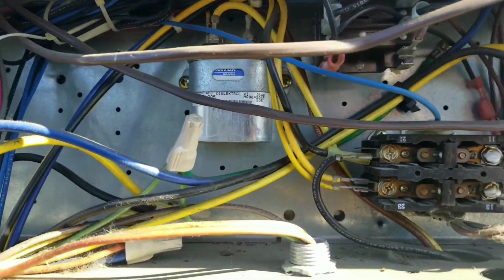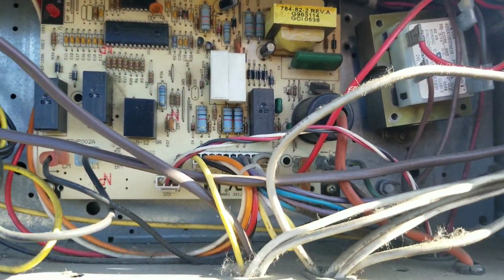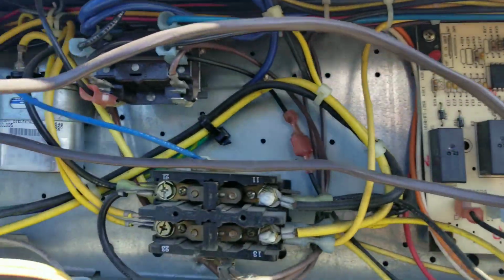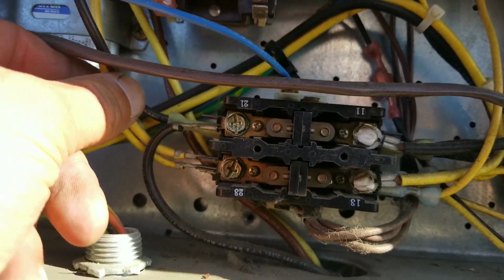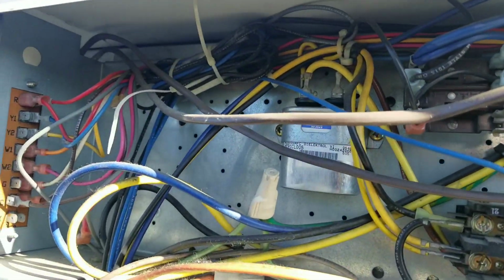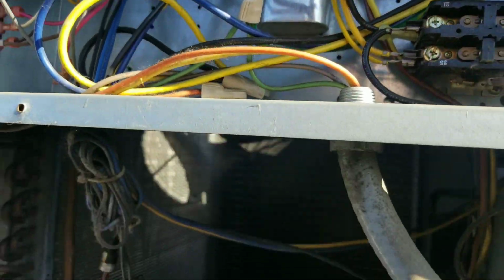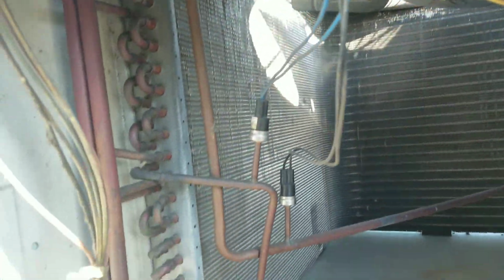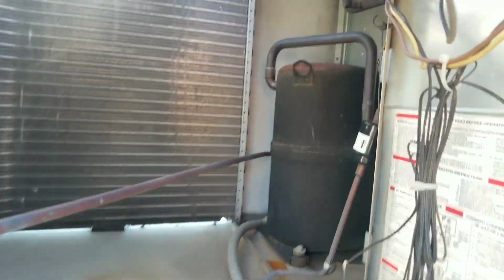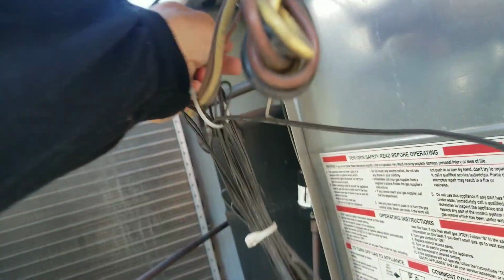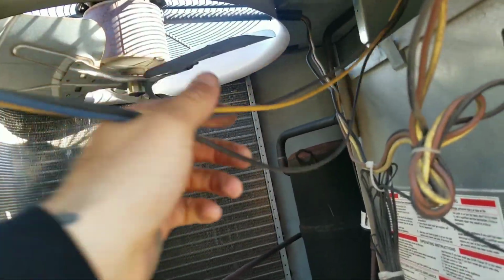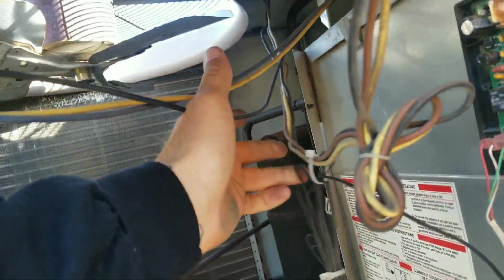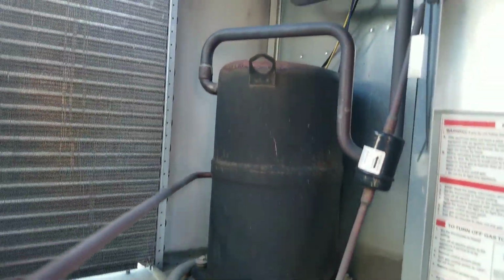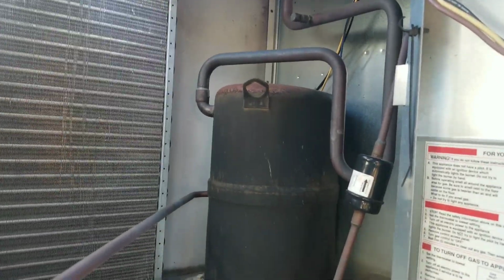Alright, so first, visual inspection. I don't see anything obvious. Nothing burned through. No obvious arcing. Transformer hasn't caught on fire. Board looks good. Contactors look good. No loose terminals on my contactor. Capacitor, it's not all puffy, so that looks good. Check down here. Really, I'm just checking for rub-throughs. Anything obvious, you know. Any place where wiring touches metal, that's alright. It's not rubbed through. But see this wiring right here, how it's all floppy like that? We'll have to address that. We'll find a way to tie it up and keep it from rubbing on everything else. There's a compressor. We'll get around to the other side, pull that panel off, and check that compressor in a minute.